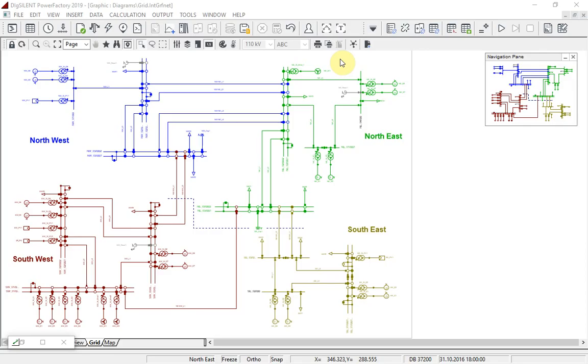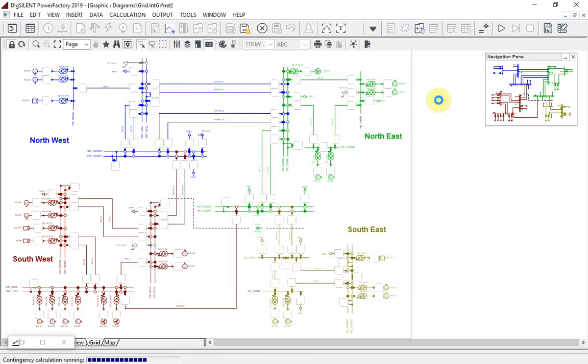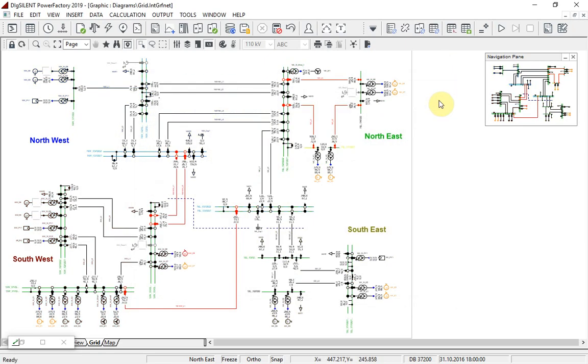I would now like to show you a couple of other enhancements to existing analysis functions. For contingency analysis, a new calculation method is available. This linearized calculation method is much faster than the more accurate iterative AC method, and so can provide a useful starting point for the analysis of large numbers of contingencies.